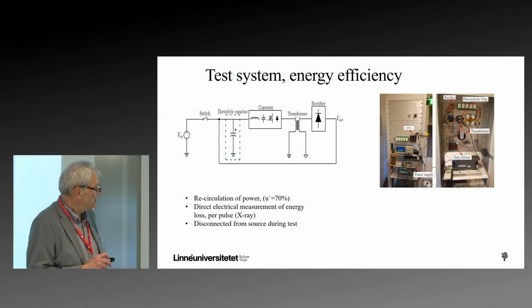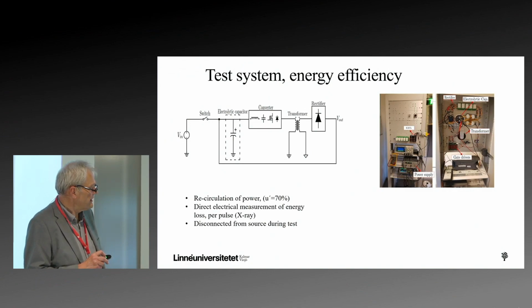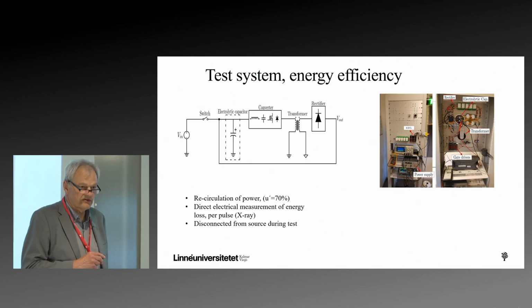And that is quite typical for this 100 kV pulse. But what this enables is that we can choose to have the same output voltage as we have input voltage, meaning that we can just recirculate the output power to the input. So the generator loads itself. And that means also that what comes here is only the losses. So we can directly measure the losses.